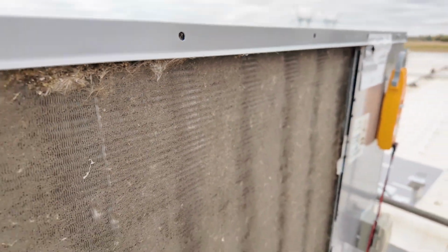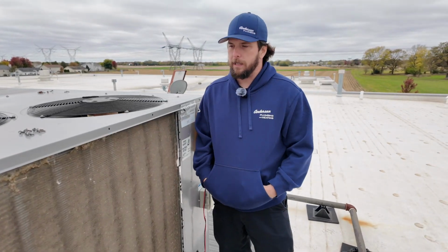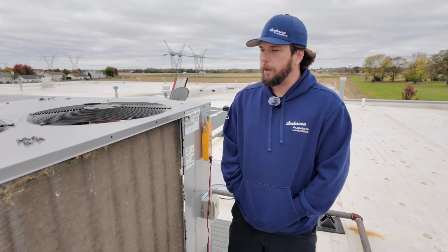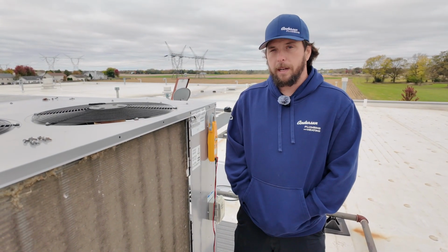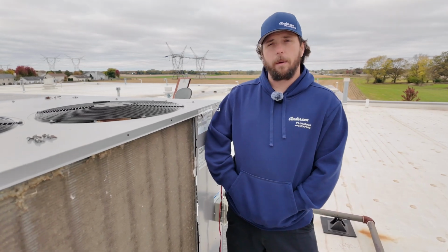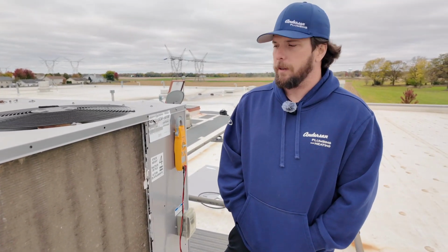So that's how you end up having performance issues. Units can't keep up because they're not breathing properly. And it eventually leads to a breakdown. It leads to a lot more stress on the equipment too. The equipment's got to run harder to do its job when it's not working efficiently.